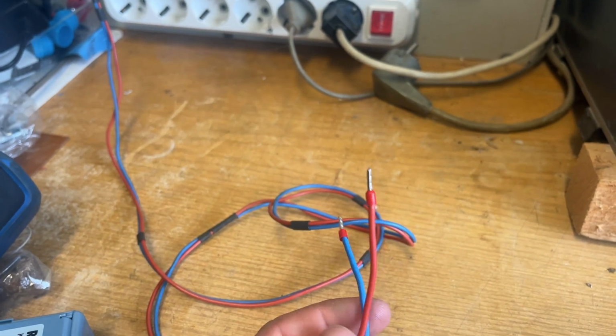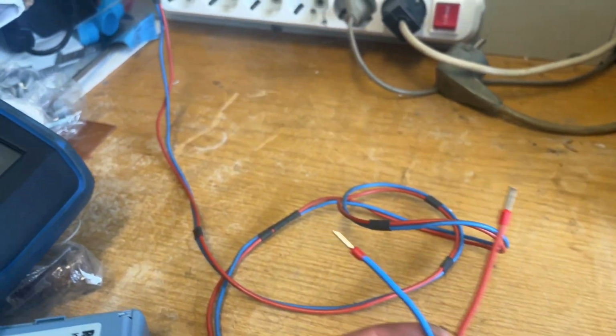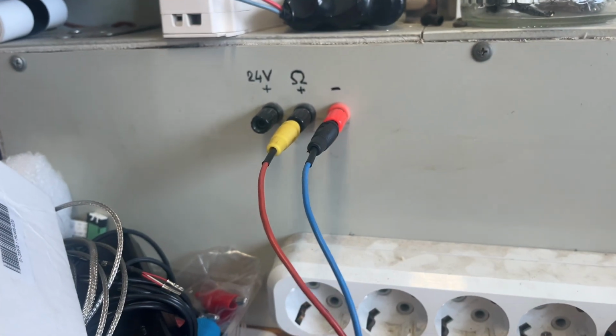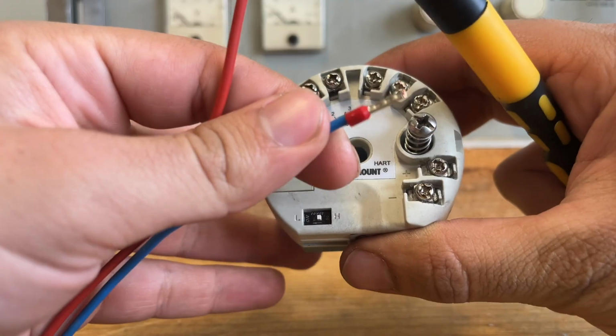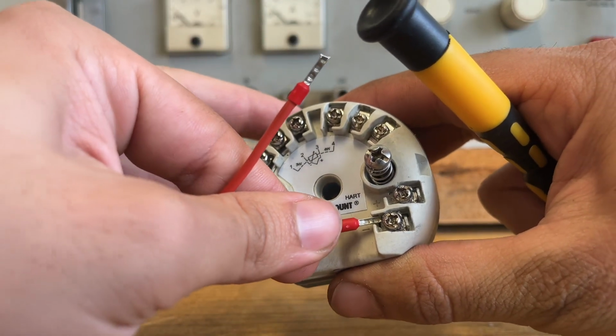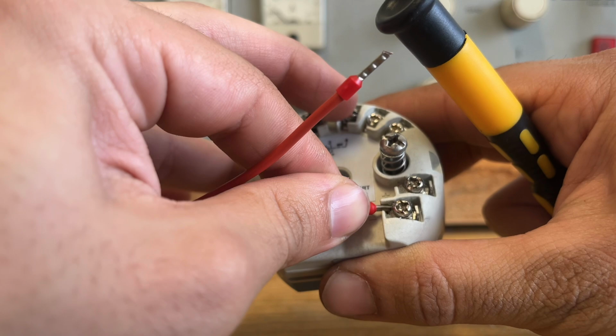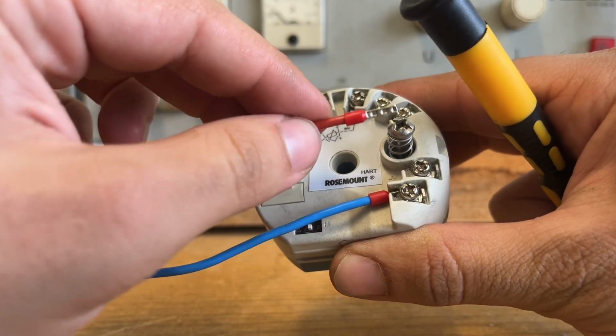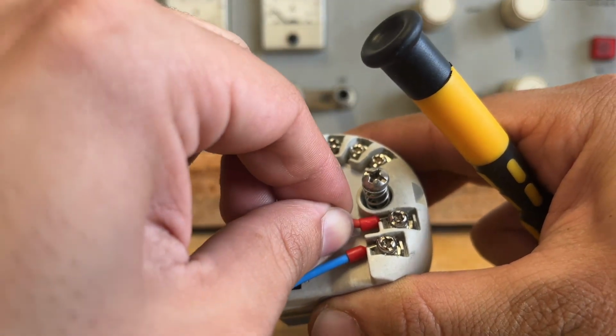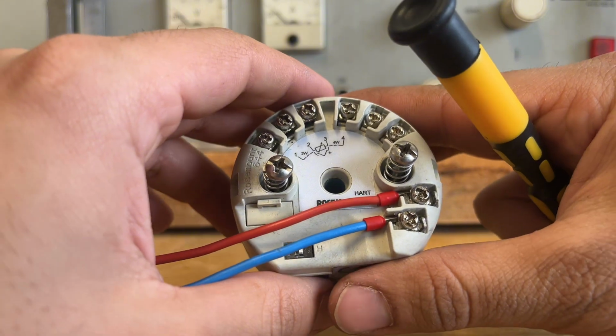Now let's connect the power supply. I'll power this transmitter using a 24 volt DC power supply, which has an embedded resistance needed for HART communication. The positive plus terminal of the power supply goes to the plus terminal of the transmitter, and the negative minus terminal to the minus terminal of the transmitter. Now that power is connected, let's check the data sheet to ensure we wire the RTD correctly.